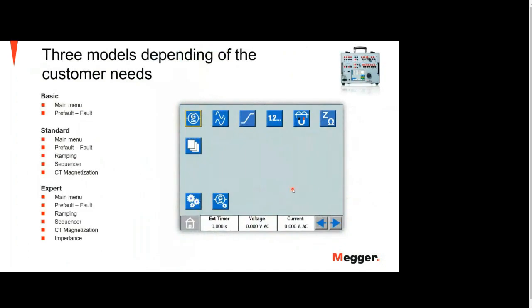We have three models of Sverker 900: the basic, the standard, and the expert. Basic includes the main and pre-fault instruments. The standard one also includes the ramp, sequencer, and the CT magnetization. And the expert one includes all, and that also includes the impedance instrument, which could be used for testing distance protections, for example. It's like manual testing of a distance protection.